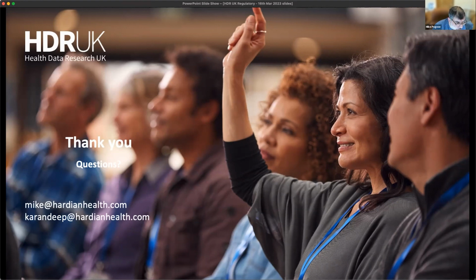The first one. Question: tiers of change. How much change to the clinical language and performance of the AI models underlying a chatbot would count as tier 0 versus tier 1? I always say it depends. And this is why we say at every prospective change, there's a structured way to do change impact analysis. You go through and say, what is it you propose to change? What's the narrative? How does it actually change the risks that you've registered? And then you can decide perhaps if it's a tier 0, tier 1, or tier 2.